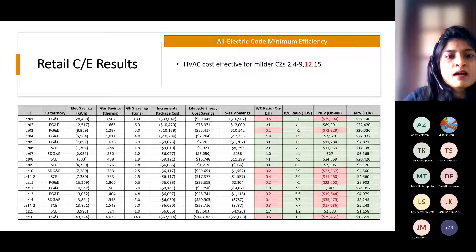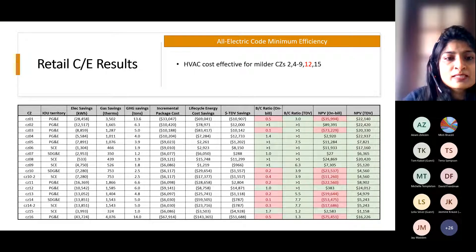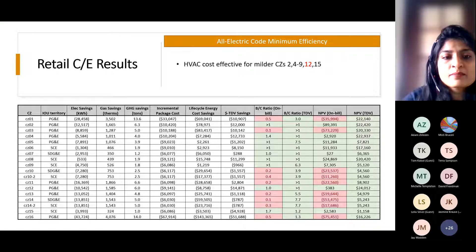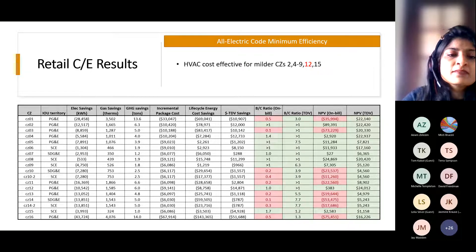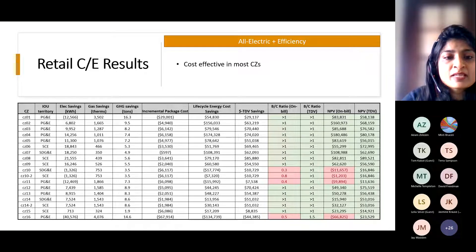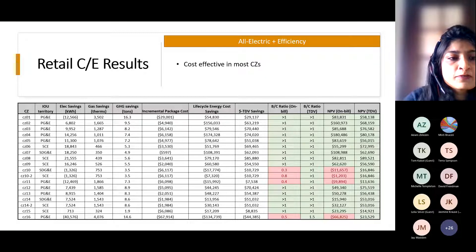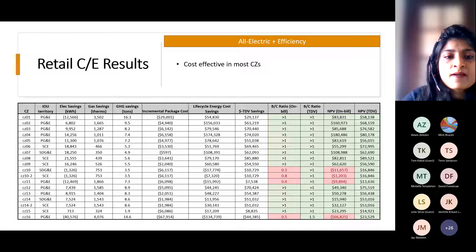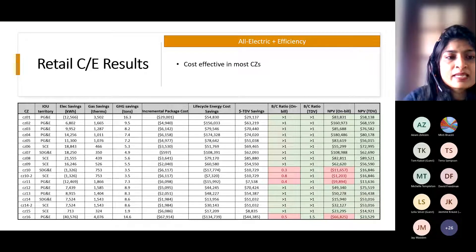For retail, it is cost-effective based on HVAC electrification alone for a few climate zones on on-bill basis — climate zones 2, 4 through 9, 12, and 15 — because of the first cost savings. TDV cost-effective for all climate zones. Adding efficiency measures to the electrification package gives cost-effective results for almost all climate zones. On-bill, a few climate zones like 10, 11, and 16 are still not cost-effective, so we may be evaluating additional potential measures in the next round.